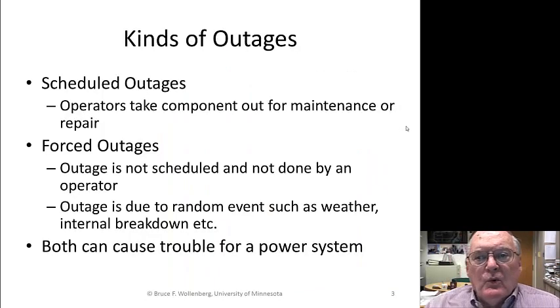Okay, what are the kinds of outages that can occur? We might need to take a transmission line out for servicing. We might need to take a transformer or a circuit breaker or a disconnect and so forth. We might need to take them out on a certain schedule for people to get in there and isolate it, ground it, and then work on it. You have to be very careful of scheduling the outages, and you have to study the system and say, if I take this out during the daytime, am I going to be able to get through the peak load during the afternoon? If not, then we've got to pay the construction people double time and let them do it at night on the night shift, whenever the load is low. So you have to be very careful when you take outages for scheduled work.